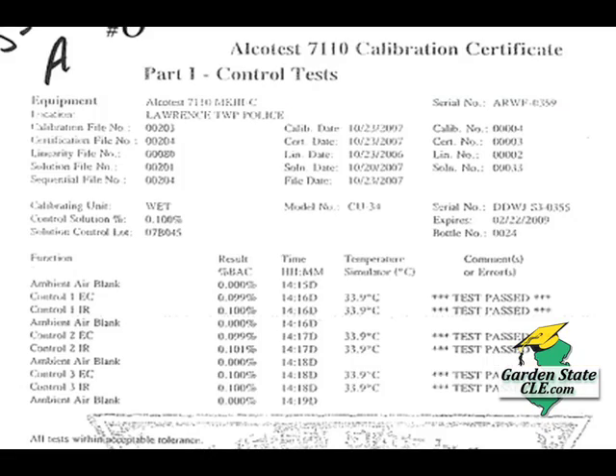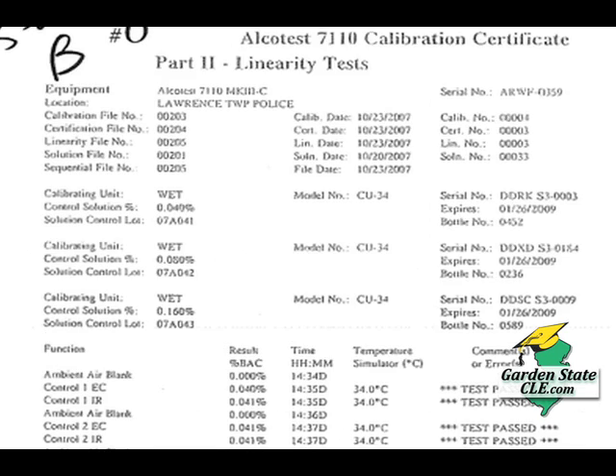The calibration record and the control tests and the linearity tests and the new standard solution report that's done at the time of calibration, the file date is going to be the same as the calibration date. But on the AIR and the new standard solution report that's done right before your client's test, the file date will be different, but the calibration date will be the same. The solution control lot, right? And the bottle number, that's going to be on all those documents. Next one is the linearity test. So this one has a lot of information on it.